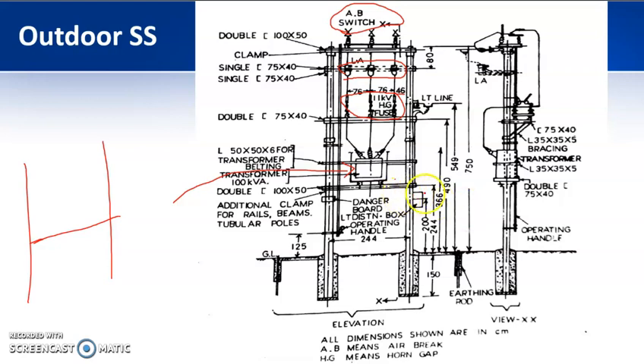So you can see here the height at which the transformer is to be kept, 2.4 meters from the ground level. The LT distribution box should be at 2 meters from the ground level, and you also have to keep a danger sign on this system to show that it is at a high voltage level. So this LT core cable you can take through a service line, or through a cable, to the inside of the substation. So this is the side view again: the horn gap fuse, lightning arresters, then your transformer, then the operating handle of your air brake switch.